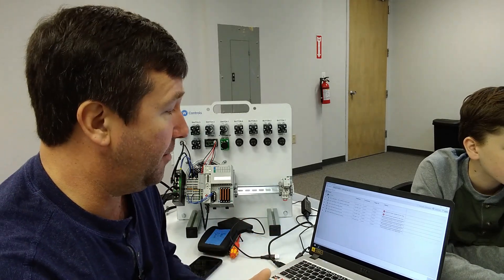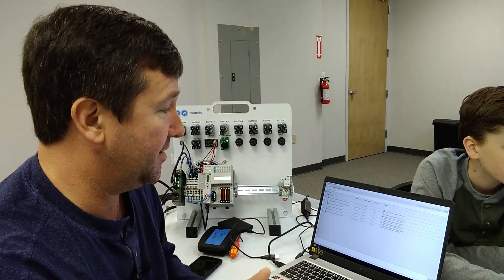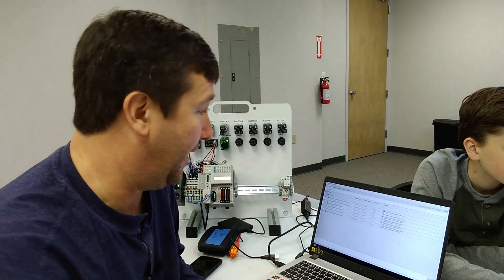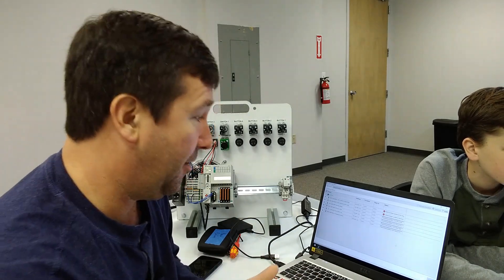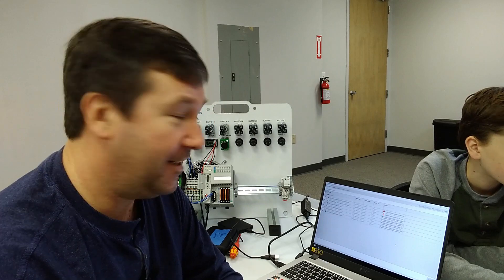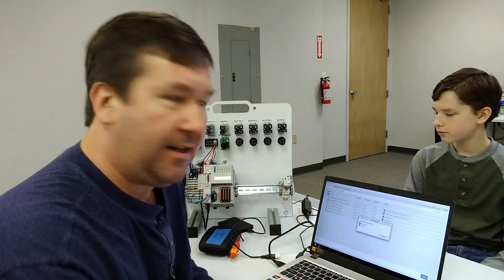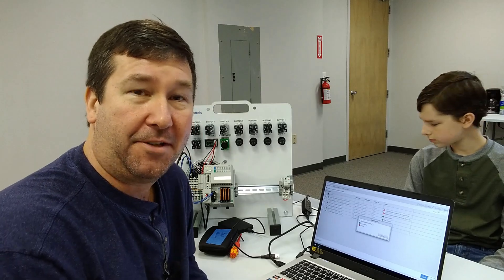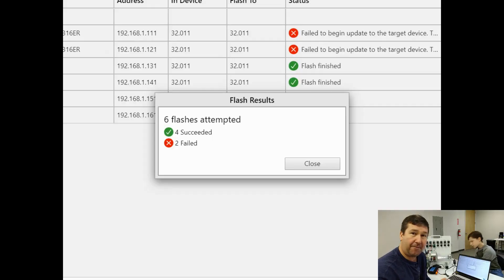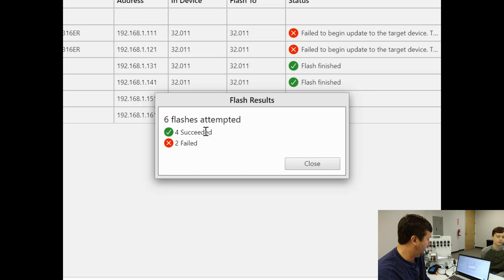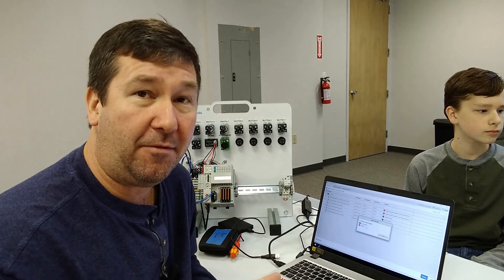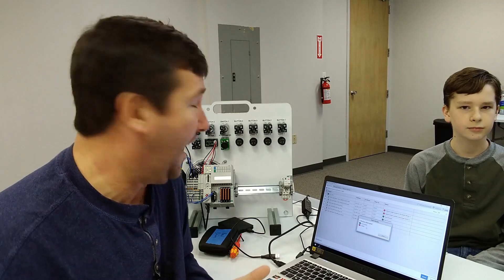Now I'm not going to worry about these two because they're already at the version I want anyway, but it does seem to do it all at one time, which is really cool and really scary. So let's see what happens. Okay. And we're done. And it shows that we have four that succeeded and we have two that failed. And the two that failed were because I had them in run mode. And I think that's kind of a cool feature is it went ahead and updated the rest of them, even though they're in run mode.